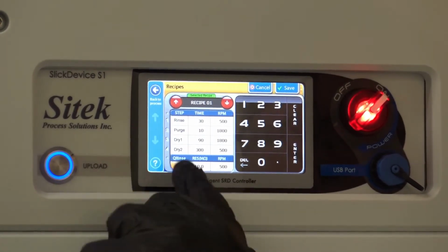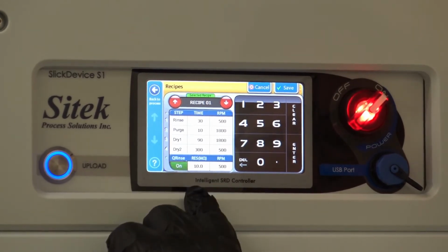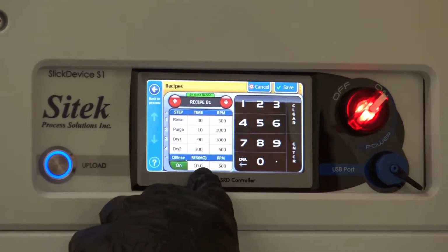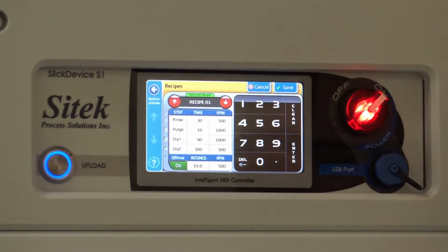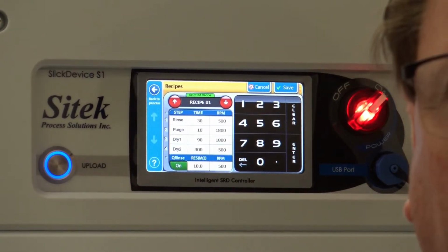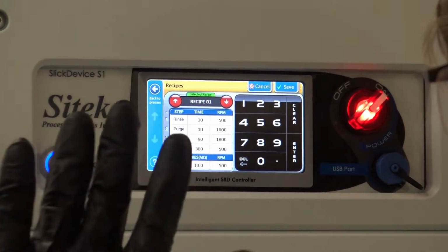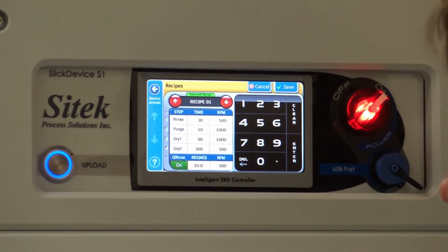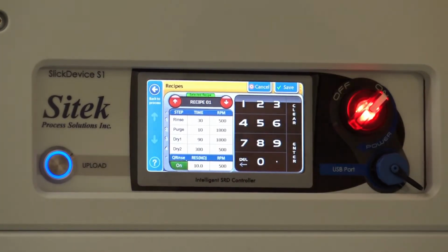It's very easy. Okay, if you want the quality rinse, you can turn it on or turn it off. What that means - right now we have it set to 10 megohms. If it doesn't reach 10 megohms in the process, you'll get a resistivity alarm on the main screen. It'll say unsuccessful run, and when you go to the alarm screen, it'll be lit up red.